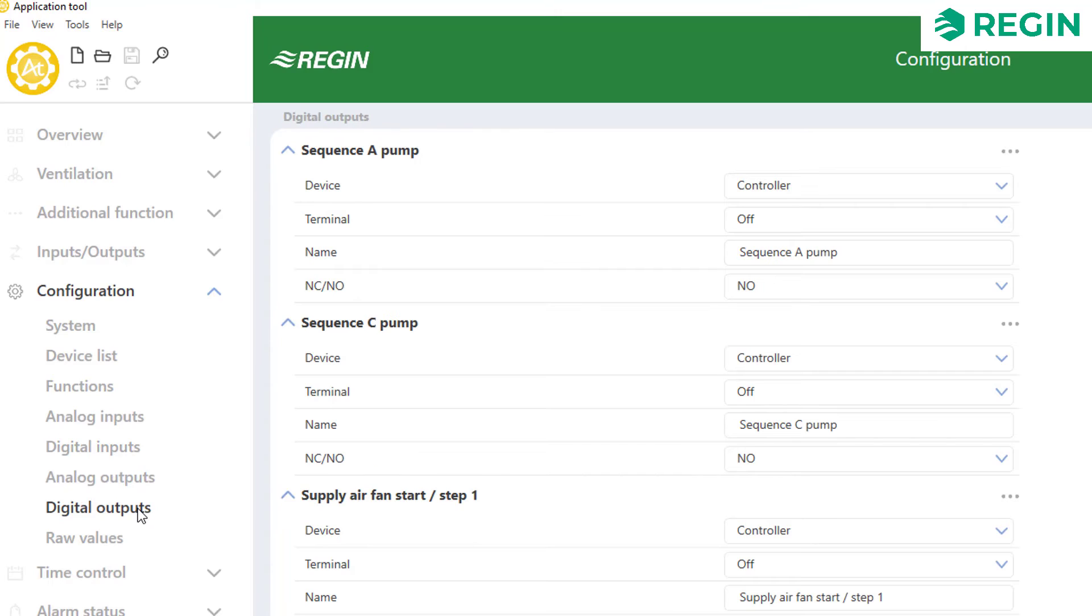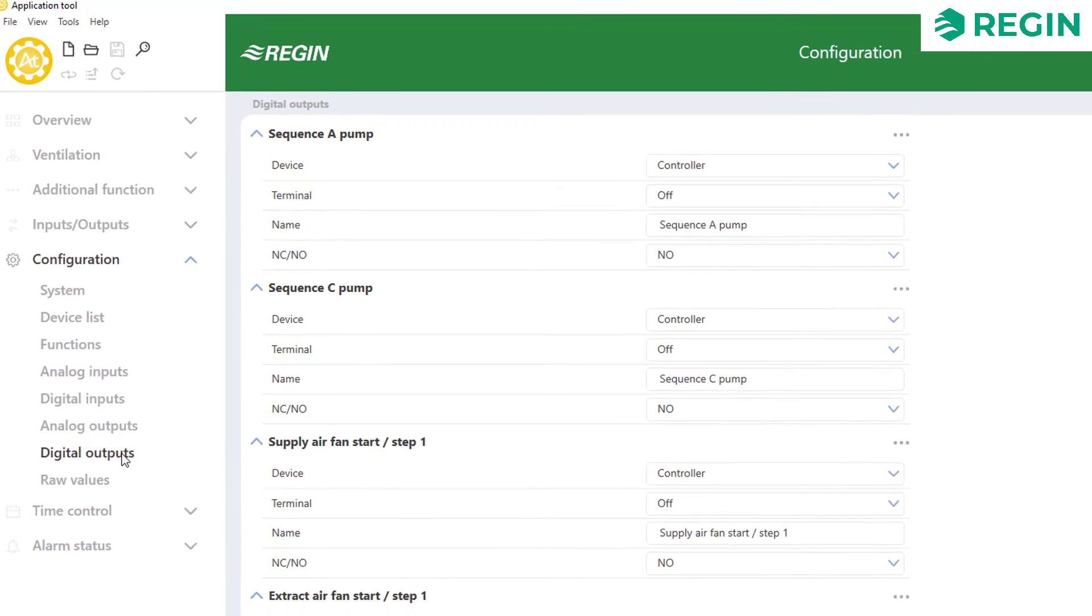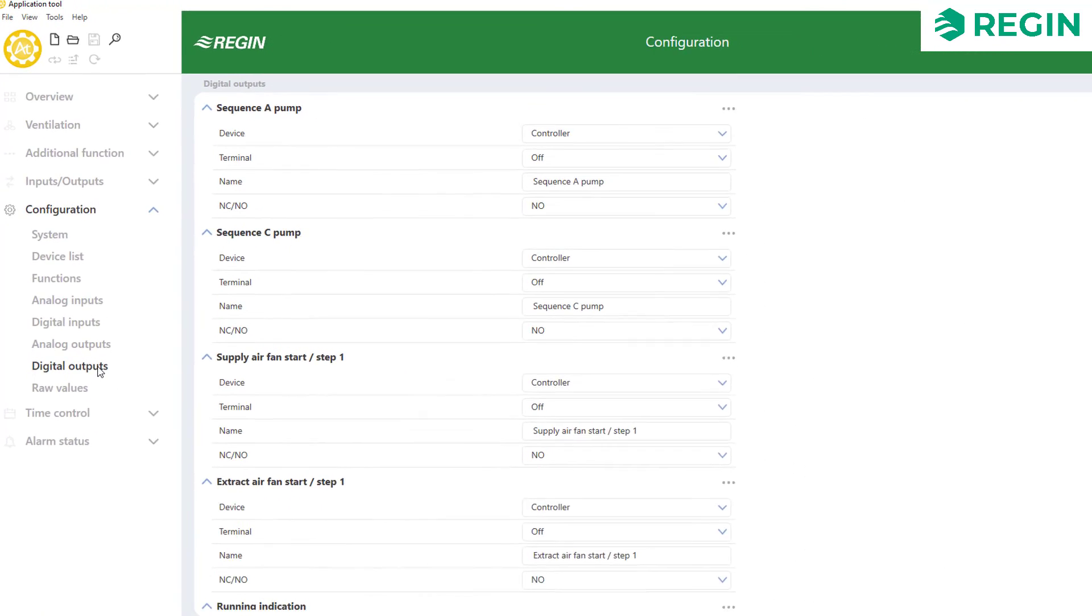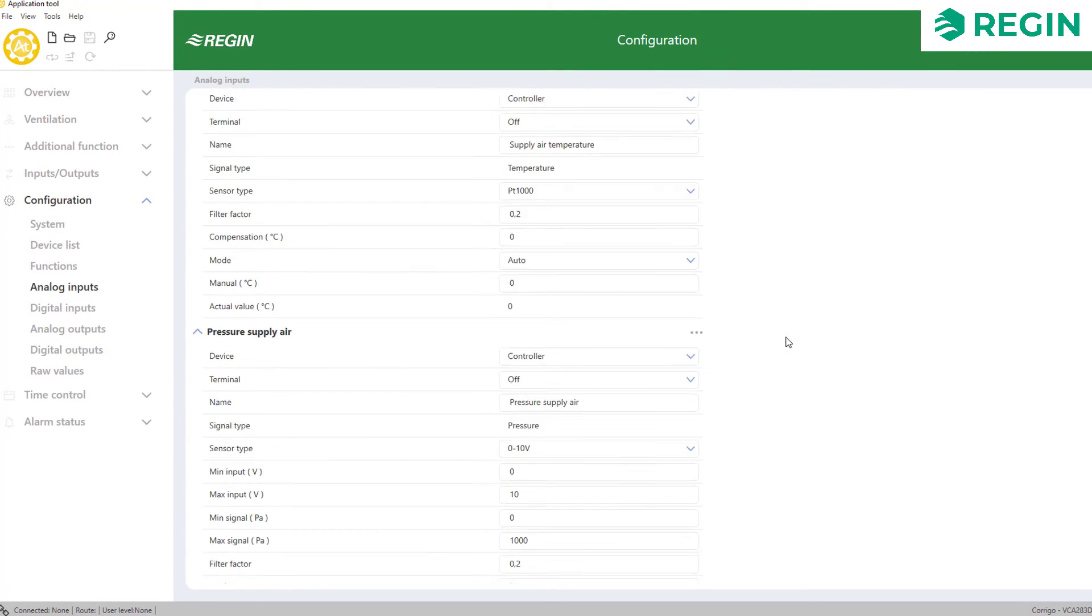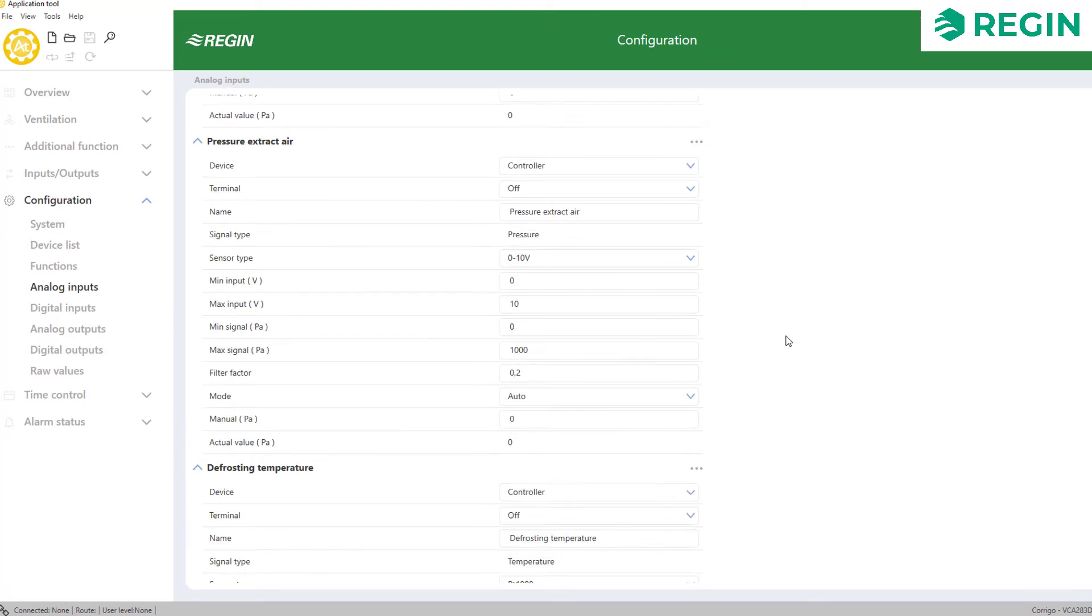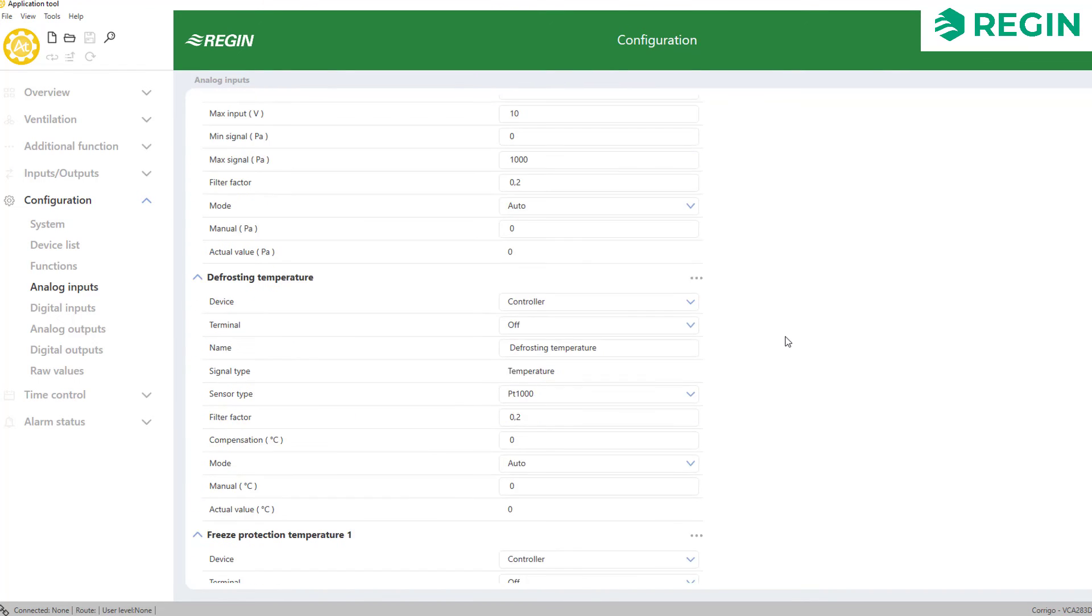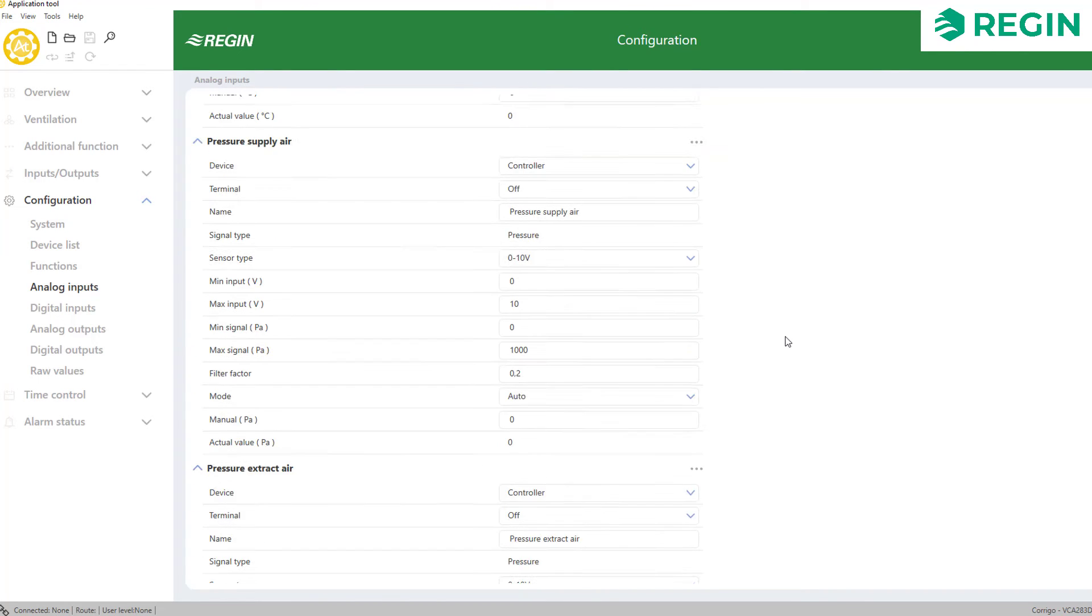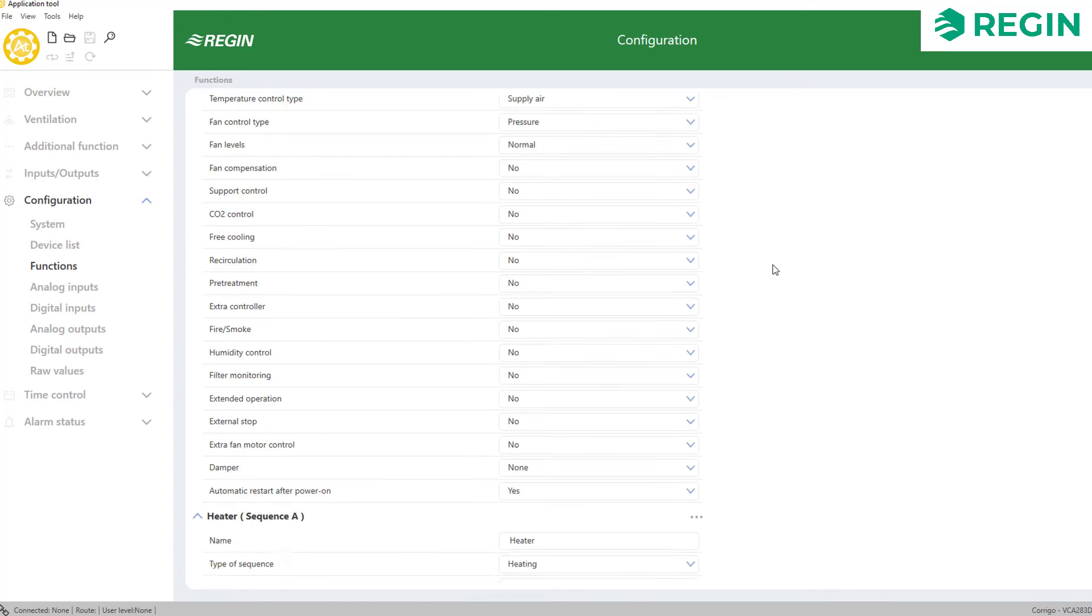This order is preferred since the configuration of one section affects which options are made available in others. For example, an outdoor temperature sensor will not appear in the inputs and outputs section unless we first enable it in the list of functions.